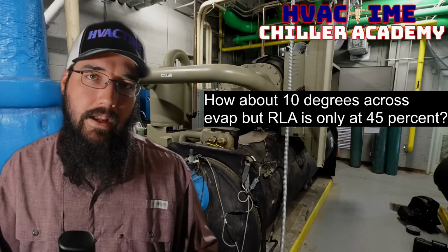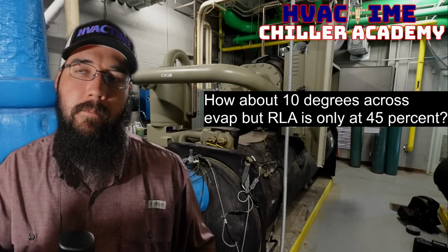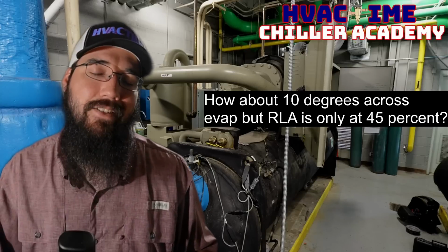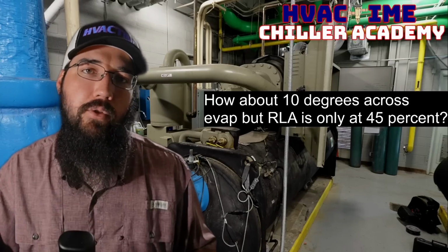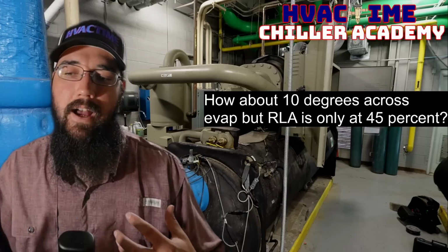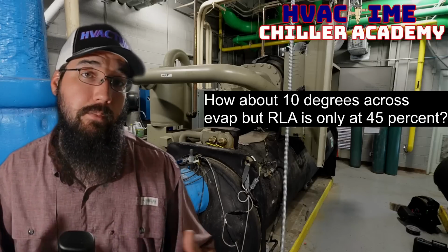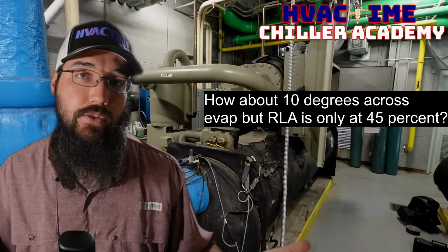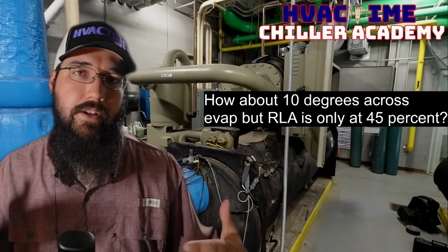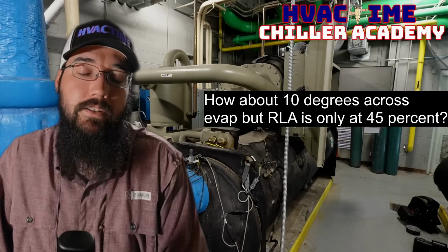So RLA is not a matter of, is this compressor running at maximum load that it could possibly handle. It is how much work is it having to do to flow the volume it's being asked for at this time. That is how I would characterize what RLA is communicating. The compressor may be able to stage up more if it needed to, but if you're making set point, it doesn't need to, but because of our lift conditions, it may not require as much work to get it there.